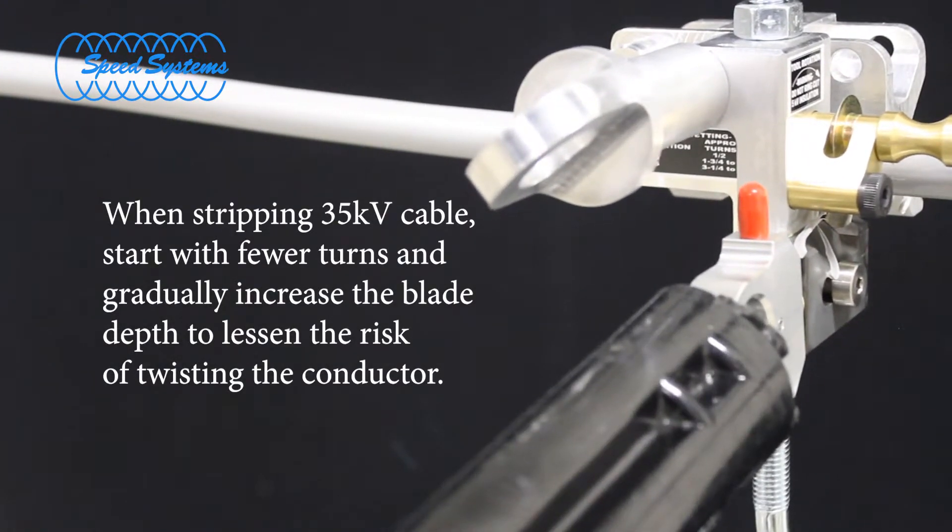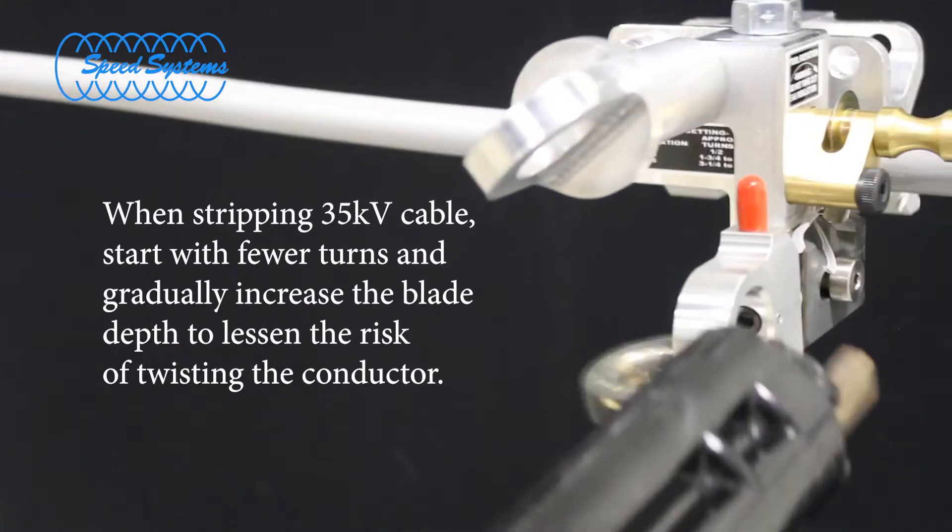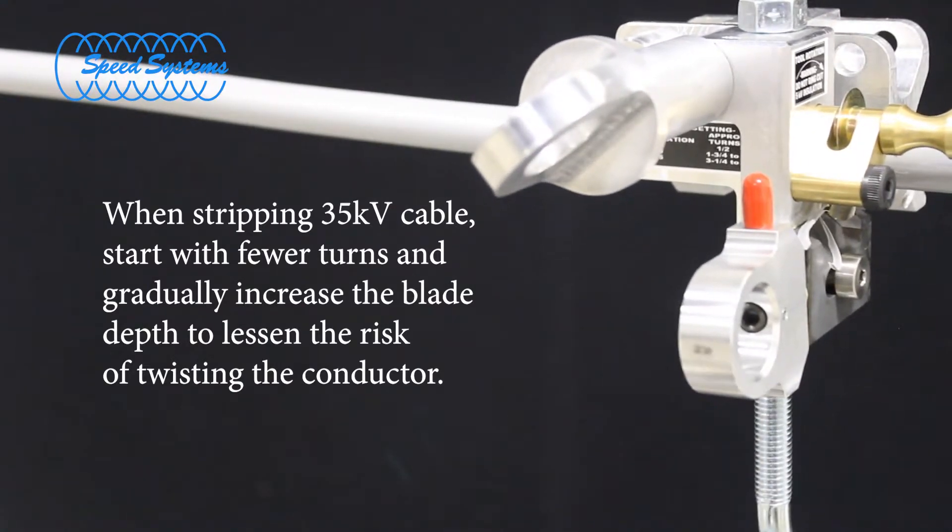For 35kV cable, start with fewer turns for the first revolution and gradually increase the depth of cut to lessen the risk of twisting the conductor.